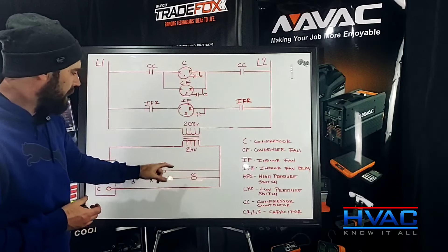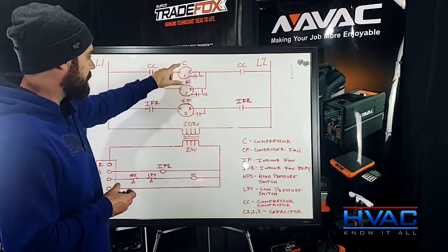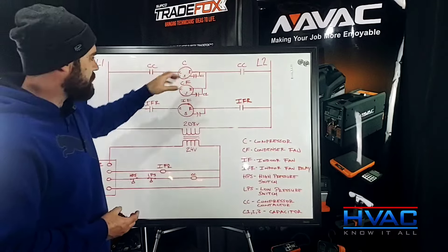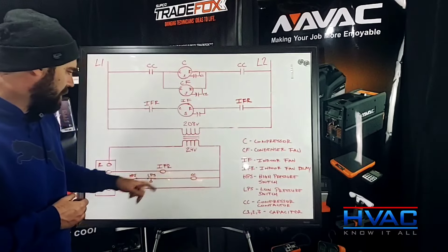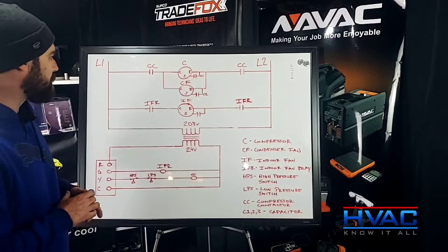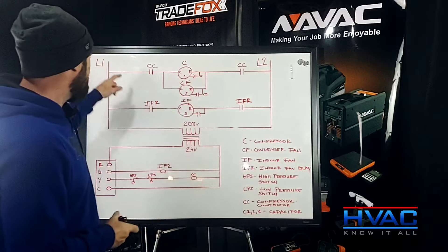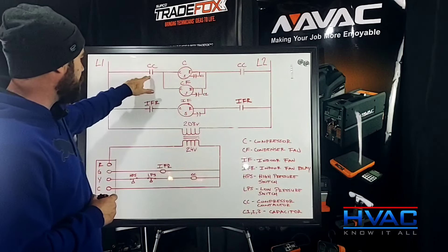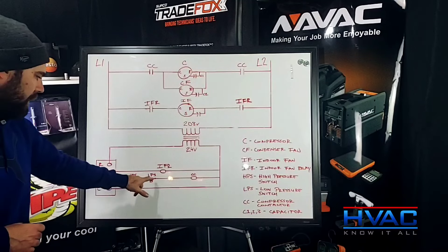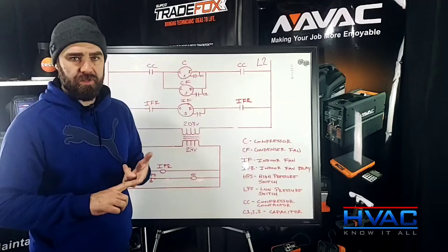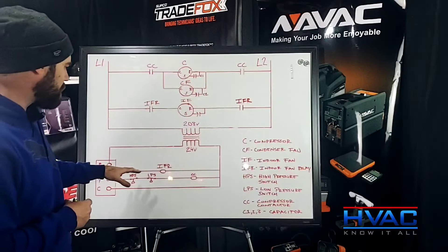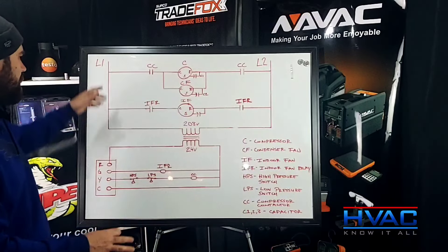These are the relays down here that you want to energize to start these loads up. We have a compressor, outdoor fan, and indoor fan. And when I say loads — a motor is a load. A contactor coil is a load. This is a switch. These are normally open contacts. If I were to draw a line through it, it means it's normally closed — that means there is continuity flowing through there. If I have an open one like this, that means we don't have any continuity flowing until we make a change. These are also switches — high pressure and low pressure switches. So in a circuit like this, we have switches and loads. Loads are receiving the power and they start to run. Switches are what close in order to relay the power through from one side to the other.